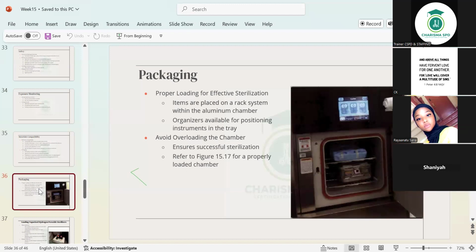A lot of times what I say during steam sterilization is, to be easy on you, if you're doing only canisters, do only canisters. If you're doing wraps, do only wraps. So if there were two canisters, you could put a canister on top and a canister at the bottom. You are safe. If there were two wrapped instruments, you could put one wrapped up and one wrapped down. You are safe. But when you have to do them at the same time, try to put the lighter ones, the wrapped one, on top and the canister at the bottom. Okay?